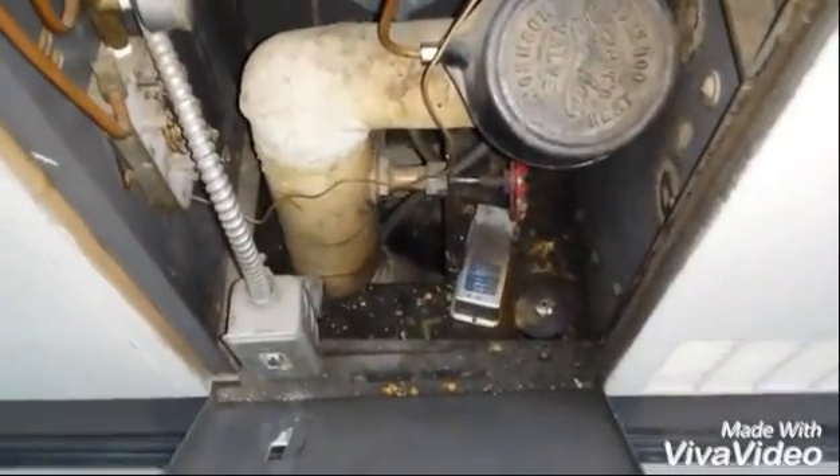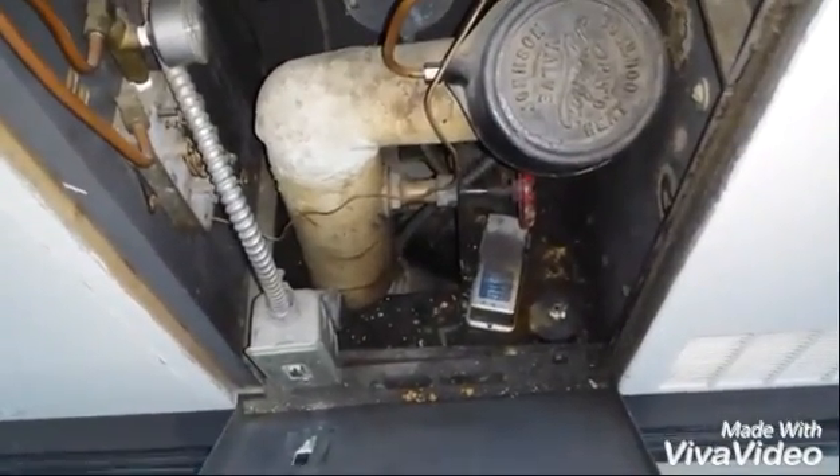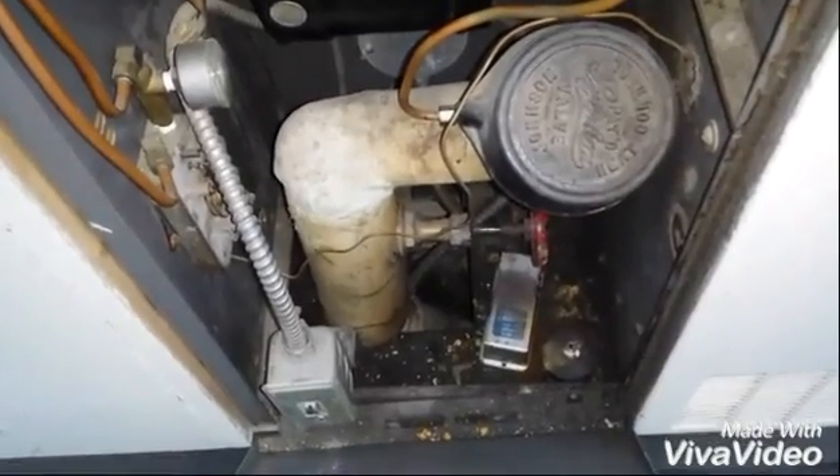Just to show you — not only is the air cell on some of the pipes, but some of the other pipes have fiberglass insulation, while the elbows are all asbestos. You just look at how dirty that is, how the asbestos... It's fiberglass by the valve, then asbestos 90, and fiberglass by the valve, then asbestos 45 as it heads down into the floor. It's just in terrible shape. There really is no other way to describe it — that is just the most friable material on a unit with a fan.